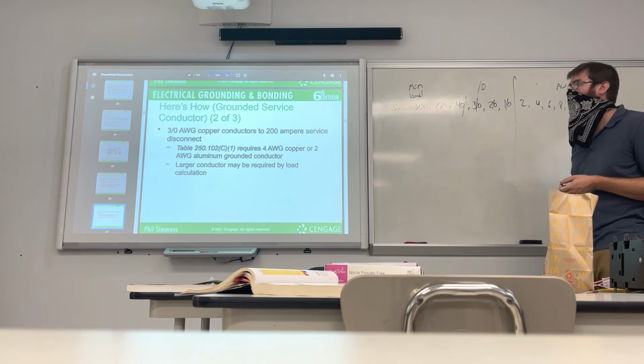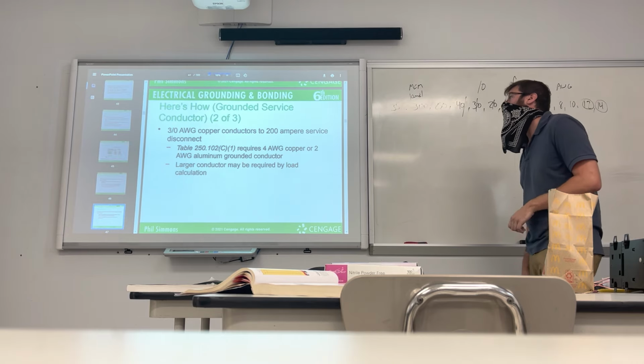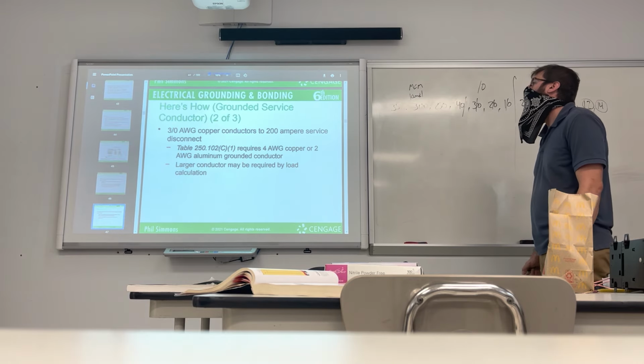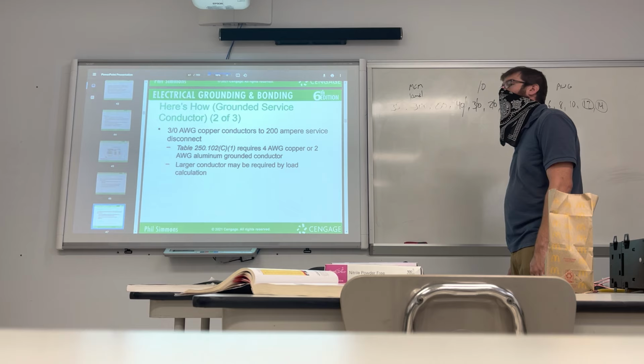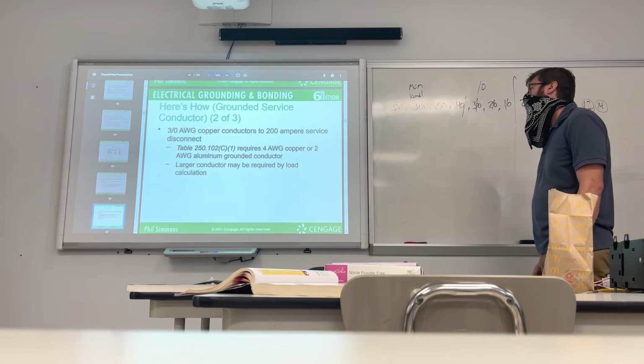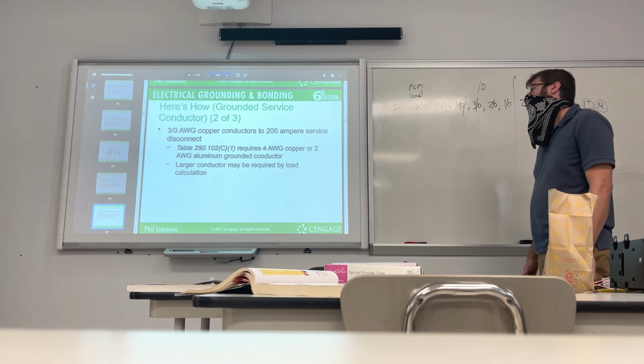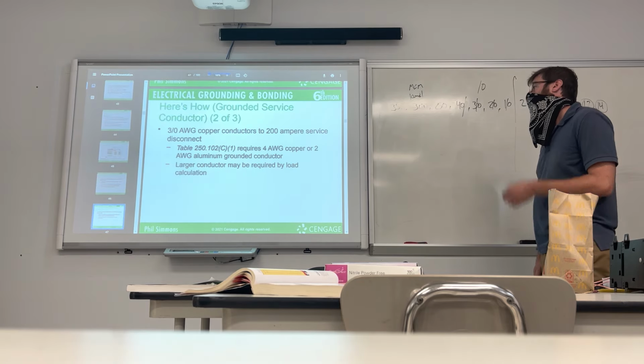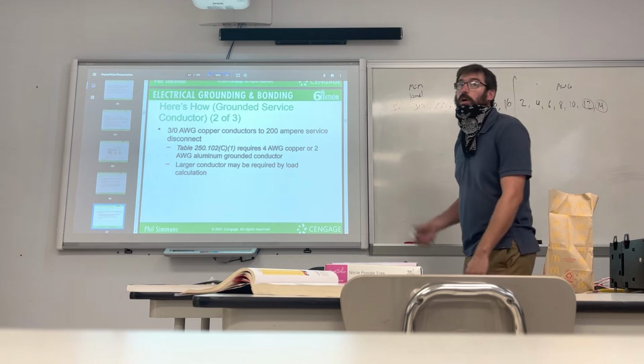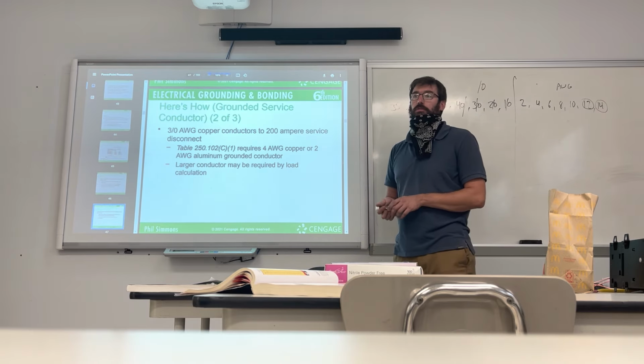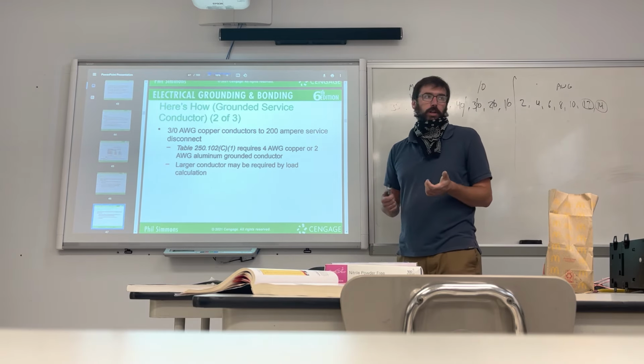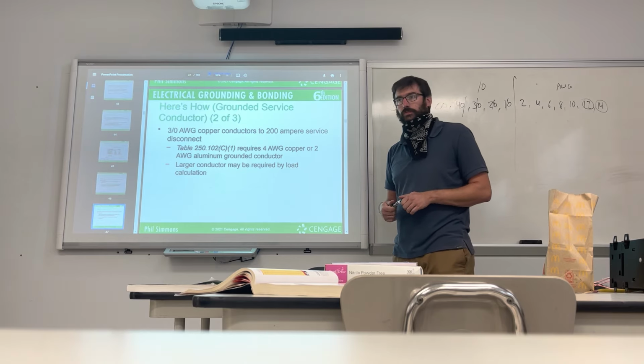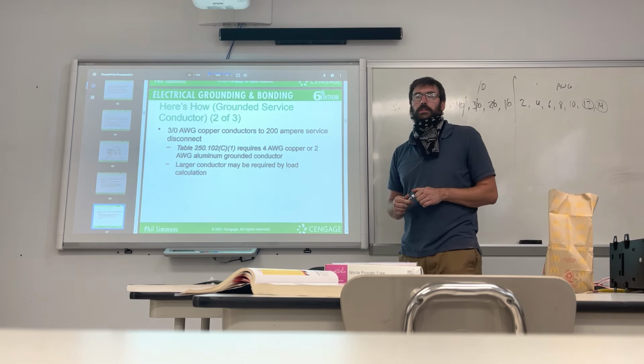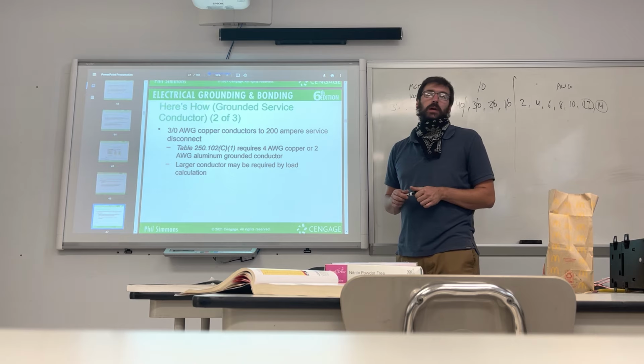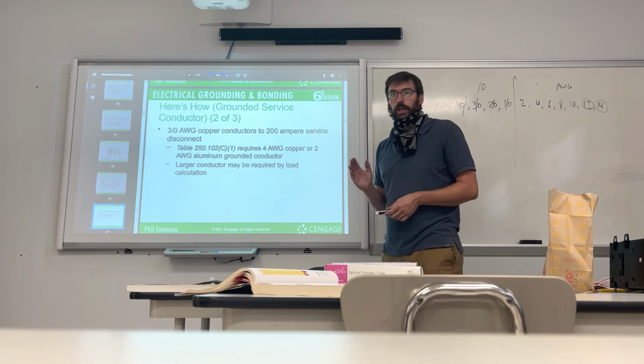Want to finish out? 3-aught AWG copper conductors, 200 ampere service disconnect. NEC requires 4 AWG copper or 2 AWG aluminum grounded conductor. A larger conductor may be required by load calculation. In most areas though, they're gonna want you to run copper for your ground. Why do you think that is? What can handle the elements better? A naked copper wire or a naked aluminum wire?